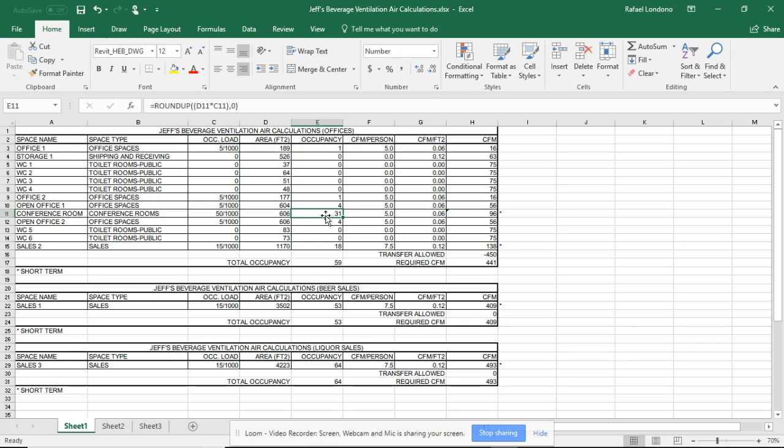But the thing about it is, you have to be careful as a designer what you label the rooms, because then the engineer is going to have to design it for that designation. I kind of fudged the numbers a little bit, but it's my professional opinion that even 31 people having a conference is a high number. Then there's the second office space, and there's another 4 people. So in the second floor, we're going to have 39 people.